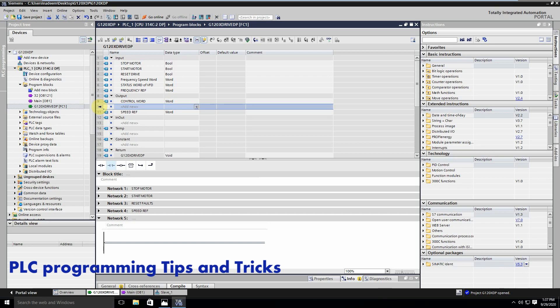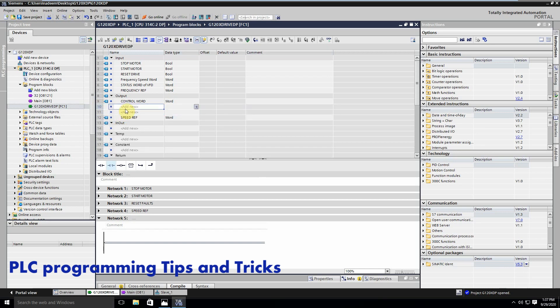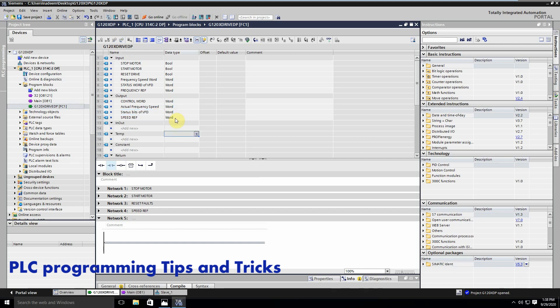In the output section we will create two more words to transfer data from the status words of the VFD so we can use them in our programming. The first output word will be named 'actual speed'. The second will be the 'status bits', which will indicate the actual condition of the VFD, and it is also of type Word.